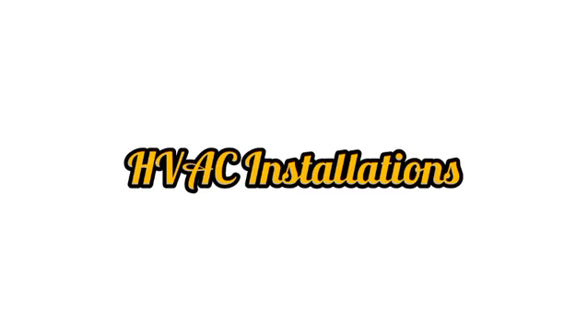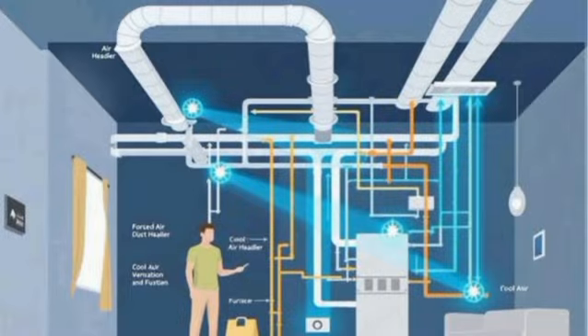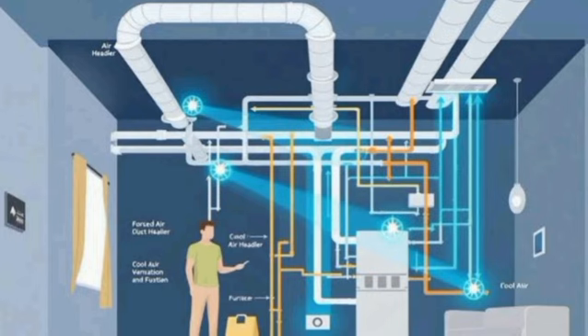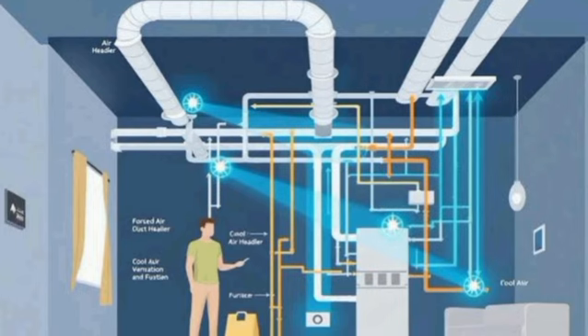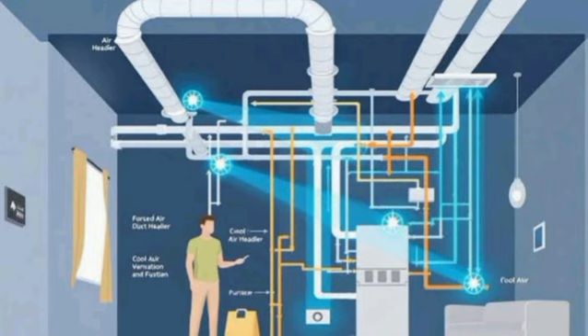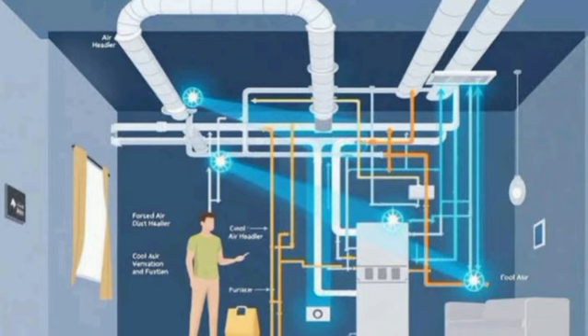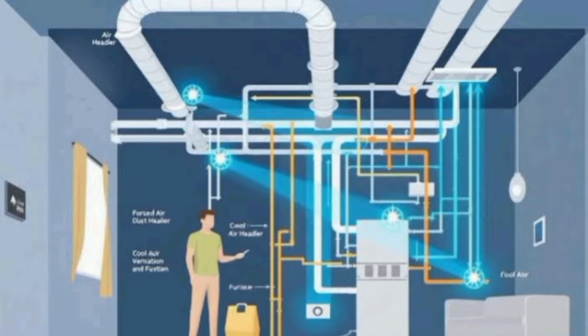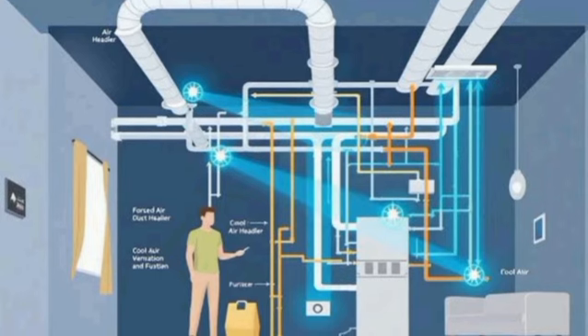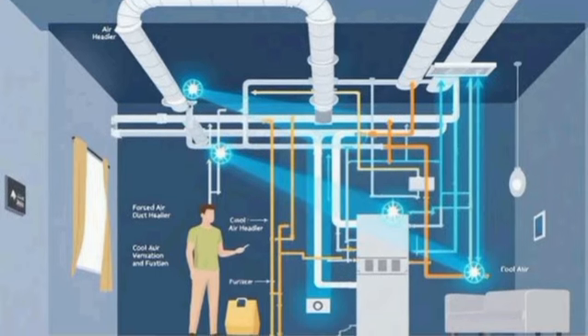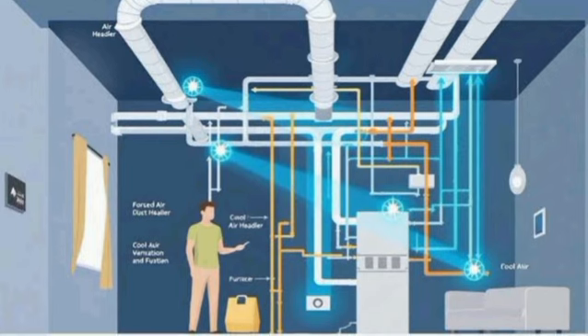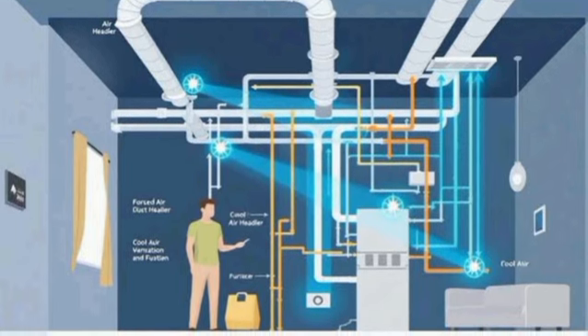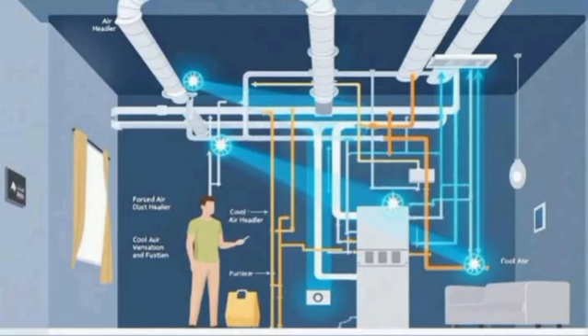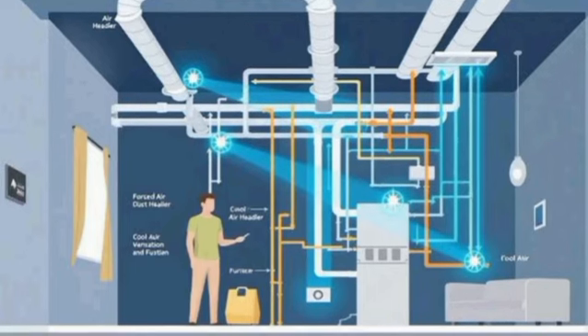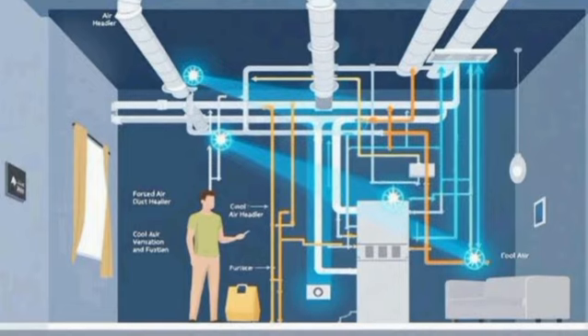HVAC installations. Large fans and air handling units draw heavy starting current. This explains why star delta starter is used in commercial buildings. It stabilizes electrical load during startup. Reduced current prevents voltage dips. HVAC systems require smooth operation to ensure comfort and efficiency. Controlled startup protects both motor and supply network.